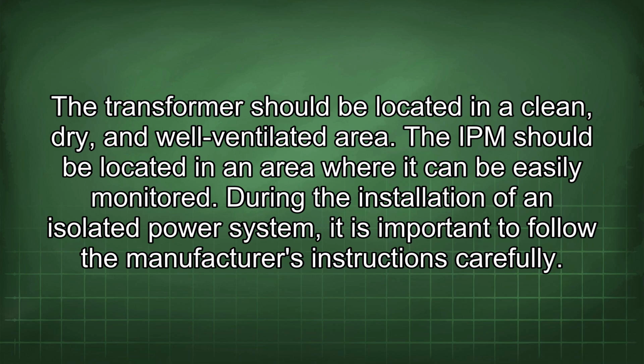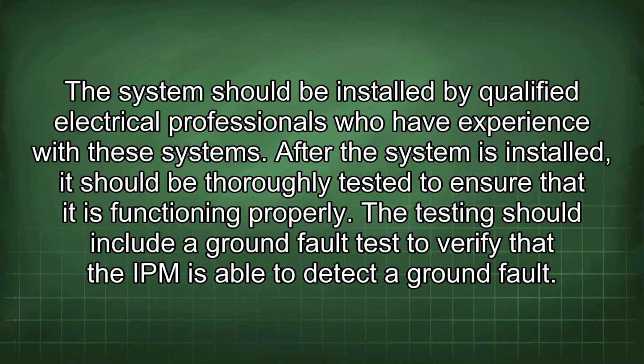During the installation of an isolated power system, it is important to follow the manufacturer's instructions carefully. The system should be installed by qualified electrical professionals who have experience with these systems. After the system is installed, it should be thoroughly tested to ensure that it is functioning properly. The testing should include a ground fault test to verify that the IPM is able to detect a ground fault.